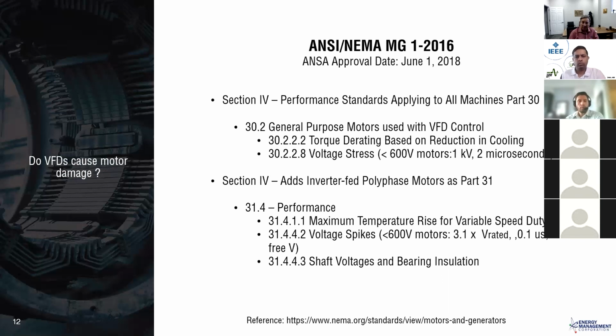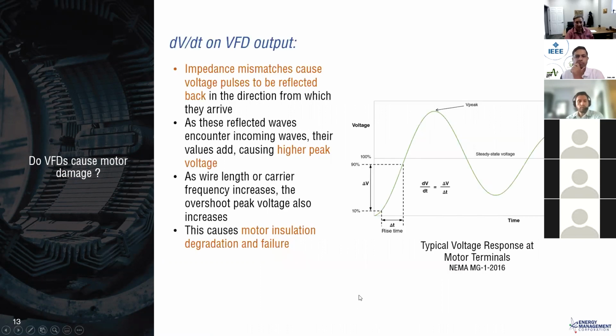And then the second part that I think is of high interest from the question is the shaft voltages and bearing currents, basically shaft currents that are addressed in 31.4.4.3. And if you want to get this exact standard, this is one of those standards that I'm surprised you can log into NEMA.org and actually download this electronic version for free, rather than paying the $659 for a hard copy. So that's a lot in one slide.